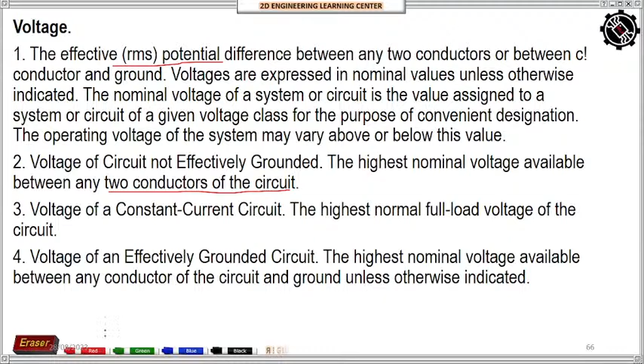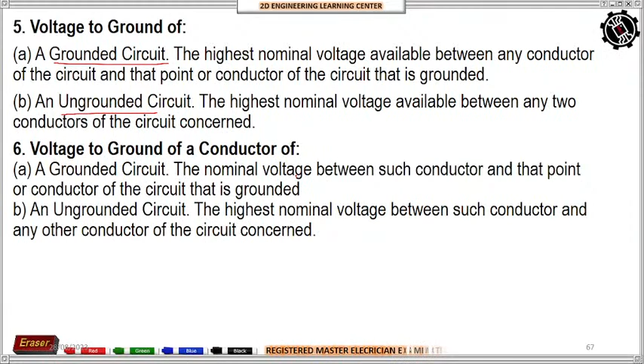Kapag voltage to ground, it will also depend if the circuit is grounded - that is the highest nominal voltage. If ungrounded naman, the highest nominal voltage between the conductors which is concerned. So kapag yung system mo is grounded system, iba yung voltage ng grounded system, iba yung voltage to ground niya compared to the voltage to ground ng ungrounded system - mas malaki ng konti yung sa ungrounded system. So voltage to ground of a conductor is the voltage between a conductor and ground.